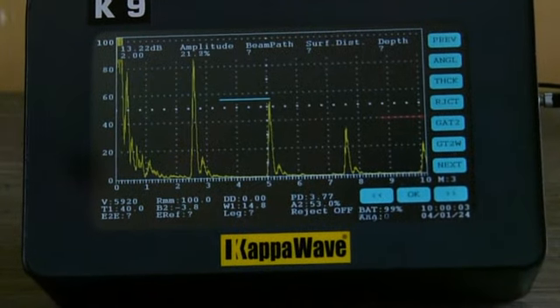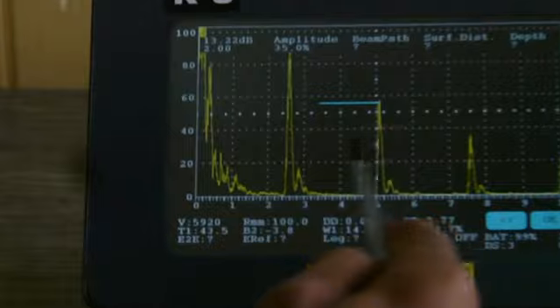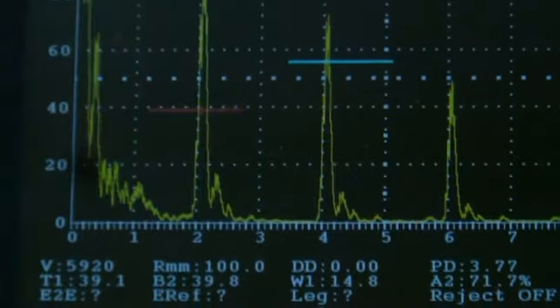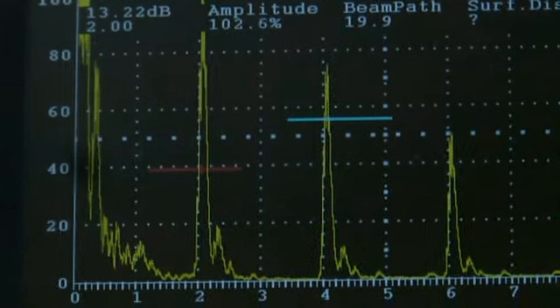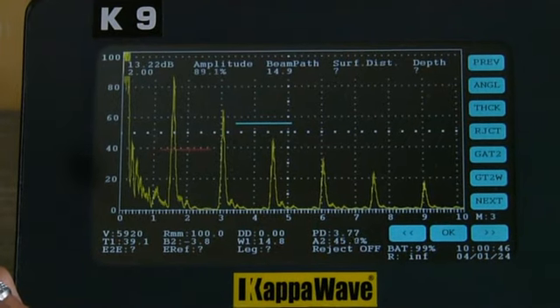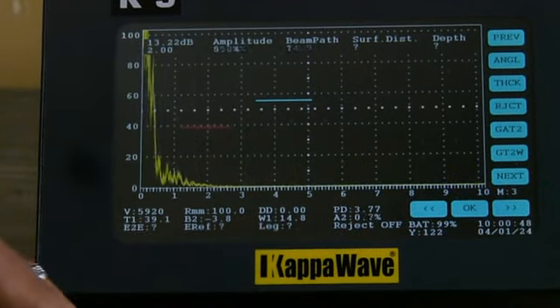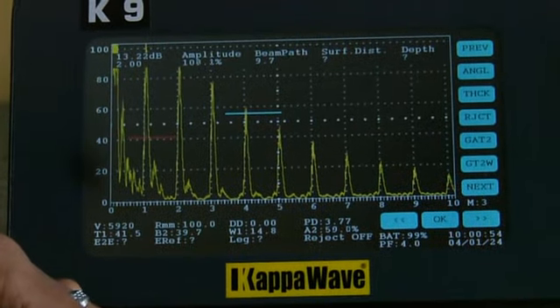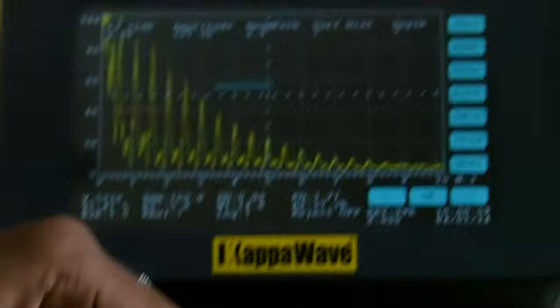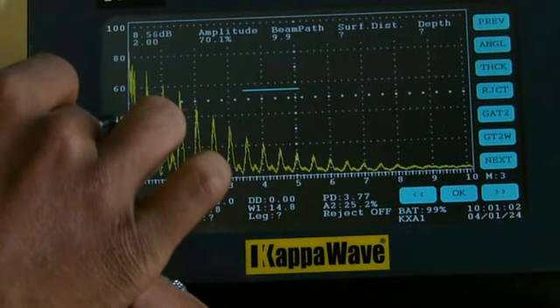Now once it is calibrated, you can actually check the thickness of other materials. I'm on a step block having different thicknesses. It's 20 millimeter thickness, 19.9, and this at 15 millimeter or 14.9 millimeter. And the next step is 10 millimeter. It shows 9.9, and the next one comes at 5 millimeter distance.